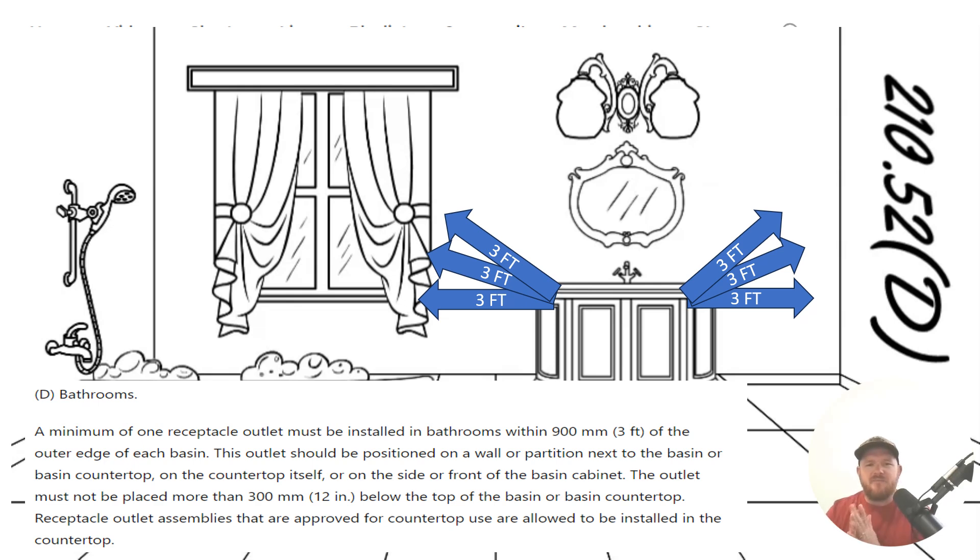Now let's finish reading the code. The outlet must not be placed more than 12 inches below the top of the basin or basin countertop. So we can't be below 12 inches there. And then let's talk about this third part here.